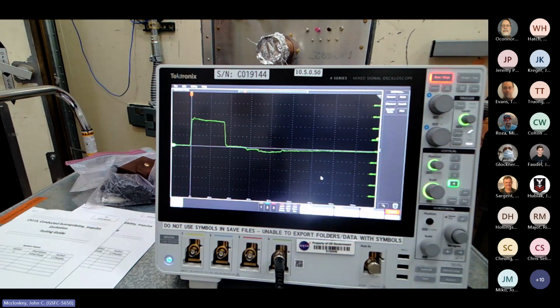It's not perfect, but it's cleaned up some. This is the sort of thing you just have to use your judgment on. If you need the full 5 amp signal, like if some external entity is saying this is the requirement and you must test to the full 5 amp level, well, it is what it is. At least with this signal generator, you won't be able to put any attenuation on. Even the 3 dB attenuator didn't allow us to get the 5 amps.